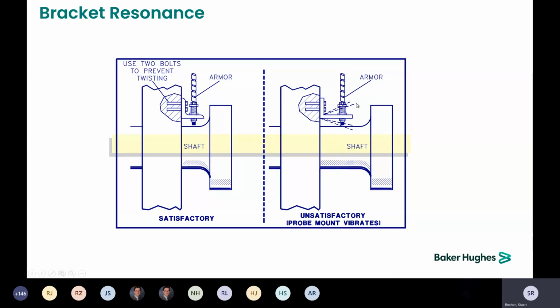That can get a bit more tricky if you have redundant probes and or have the shaft absolute set up where you may have a velometer on the same bracket as the proximity probe, and you just don't want to have that flexing or moving around.